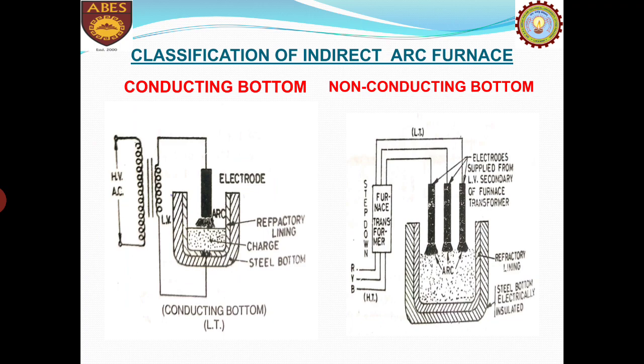Now electrically, if I talk about the indirect arc furnace, they are further subdivided into two categories. The first one is the conducting bottom and the second one is the non-conducting bottom. As the name suggests, conducting bottom means the heat transfer takes place with the help of the bottom of the vessel in which your heating is taking place, or where your charge is placed. Whereas in the non-conducting type of bottom, the bottom is completely insulated. That means in the heating process the bottom part of the vessel is not contributing at all.